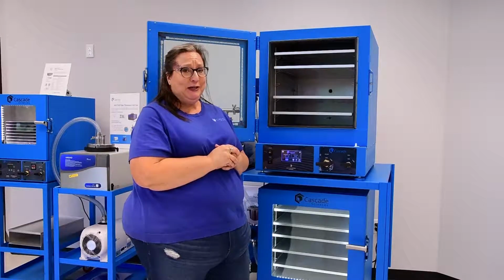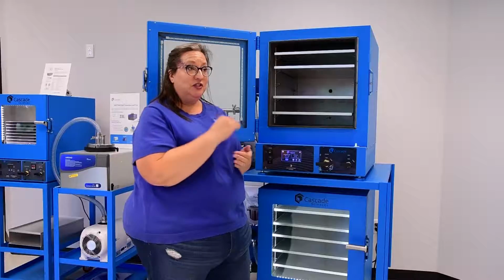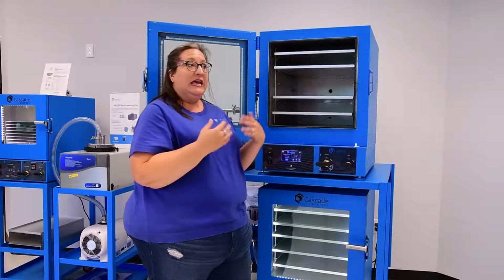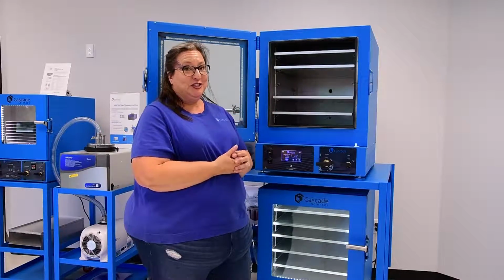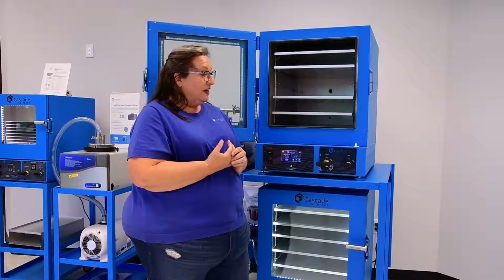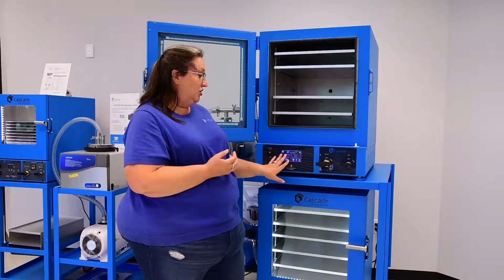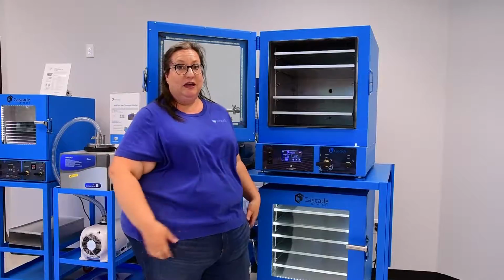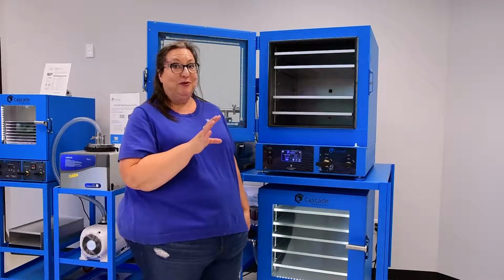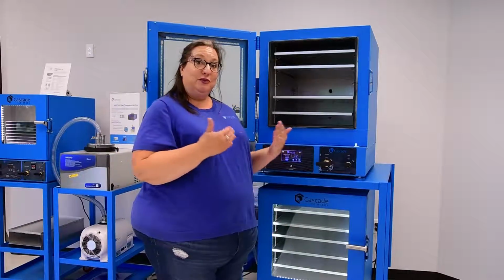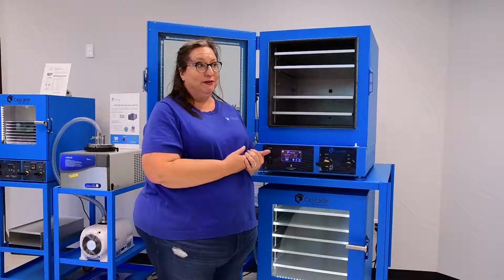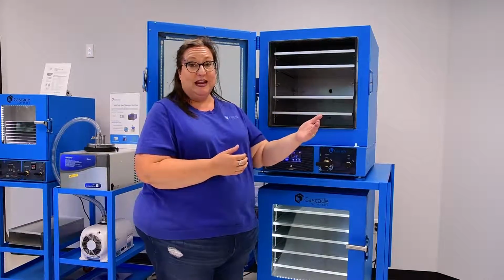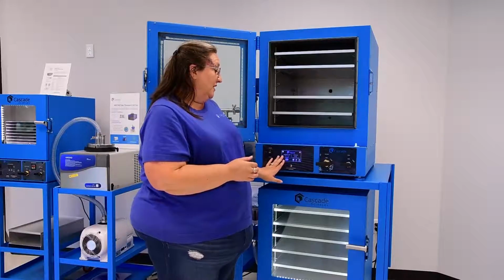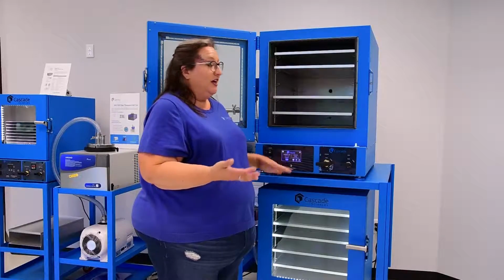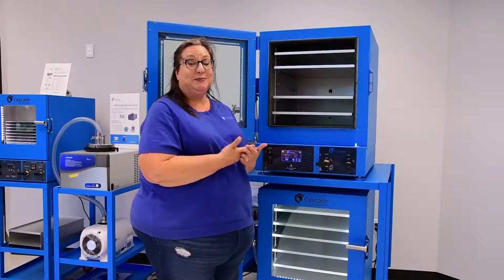I guarantee you that if your vacuum oven controller tells you that you've hit the set point in anything less than an hour, it's just lying to you. So there are, unfortunately, some manufacturers that do program controllers that after about 30 minutes, it just flashes the set point, just so that you leave it alone. But the truth is the oven isn't at temperature. And if it is, it's probably dramatically overshot it. So we're gonna tell you the truth right up front. It's gonna be low and slow, but that's by design.